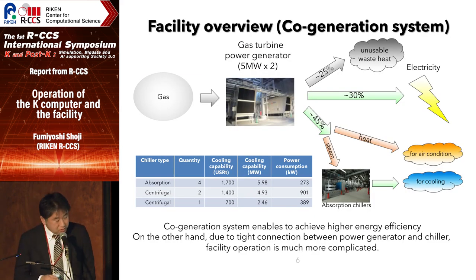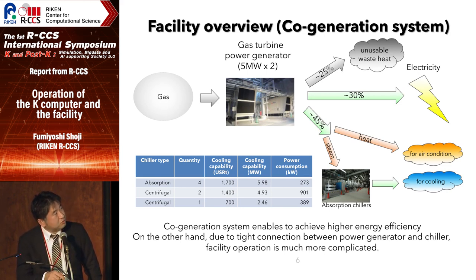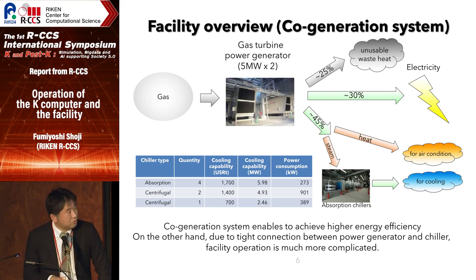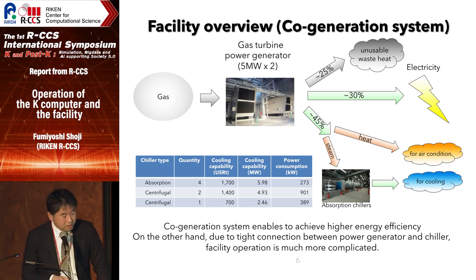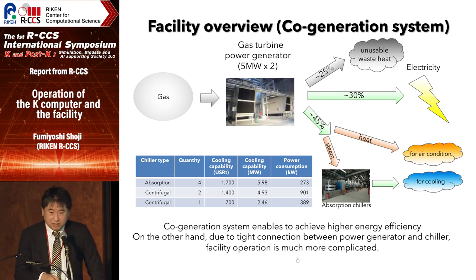This slide shows the key functions of our facility. We have gas turbine power generators. The potential energy of gas can be converted to electricity at up to 30 percent efficiency. However, our system can also use part of the waste heat — to generate heat and to produce chilled water. This kind of system is called a co-generation or tri-generation system. This system is needed to achieve higher energy efficiency, but because the power generation and chiller systems are tightly connected, operation is not easy.